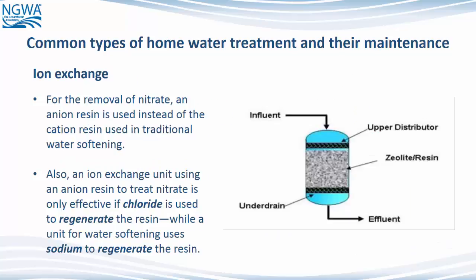For the removal of nitrate, an anion resin is used instead of a cation resin used in traditional water softening. Also, an ion exchange unit using an anion resin to treat nitrate is only effective if chloride is used to regenerate the resin, while a unit for water softening uses sodium to regenerate the resin.